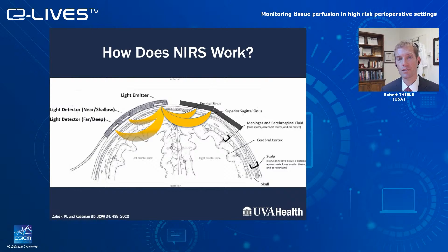Now, this is not an absolute measure of saturation of oxygen in the tissue. It's a blended average of arterial blood, capillary blood, and venous blood. And just like PbO2, it's site specific. It's really only looking at the frontal lobe of the brain, or if you put it on the calf, it's really only looking at the calf muscle. And so one of the problems with using this technology, in particular in the brain, is that if pH changes or PCO2 changes, that can profoundly affect the arterial to venous ratio, which can change this number, even if the tissue saturation hasn't changed that much.